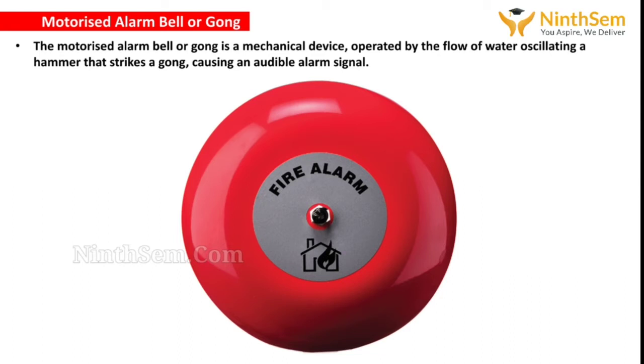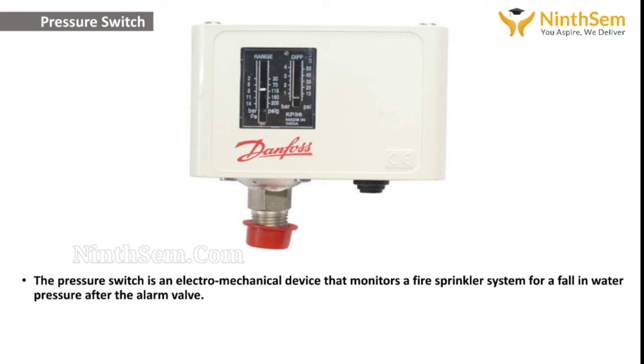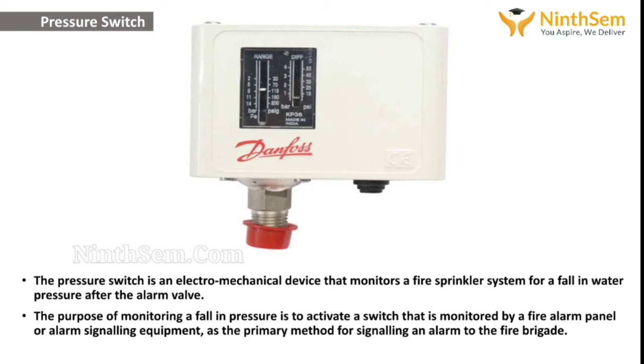Next, let's discuss some ancillary components, which we have already mentioned. The first one is the pressure switch. These ancillary components are in addition to the main components of the fire sprinkler system, and there are a series of ancillary, or we can say support, components that regularly form part of an automatic fire sprinkler system. So let's discuss the pressure switch. The pressure switch is an electromechanical device that monitors a fire sprinkler system for a fall in water pressure after the alarm valve. The purpose of monitoring a fall in pressure is to activate a switch that is monitored by a fire alarm panel or alarm signaling equipment as the primary method for signaling an alarm to the fire brigade.